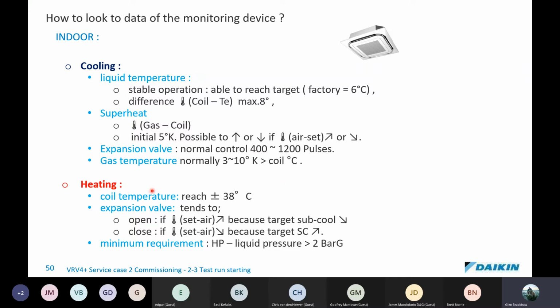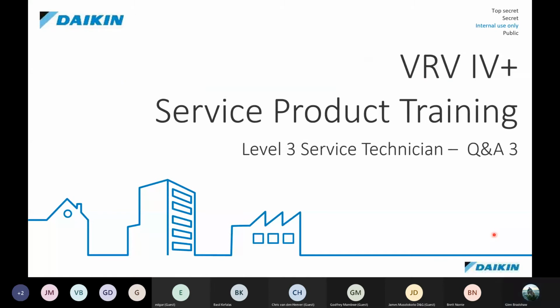Right. So on heating, the coil temperature generally tries to reach a temperature of plus minus 38 degrees, and the expansion valve is open if the set point minus the air is greater, because it's targeting the subcool. Remember, the indoor unit is now behaving as the condenser. So the subcool values are set from there, and it'll close if the set point minus the air is less, because the target subcool is greater. Then minimum requirement is HP, the head pressure, minus the liquid pressure, and this is to ensure that there's sufficient flow of liquid taking place. All right, so we've got to the end of that.